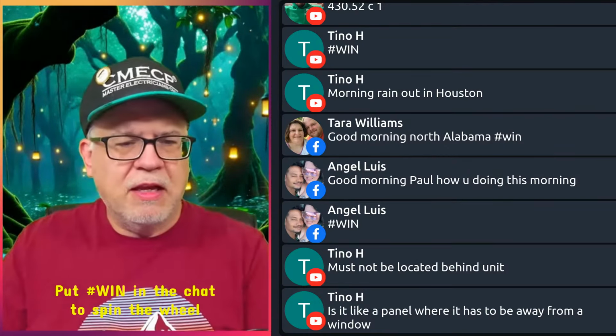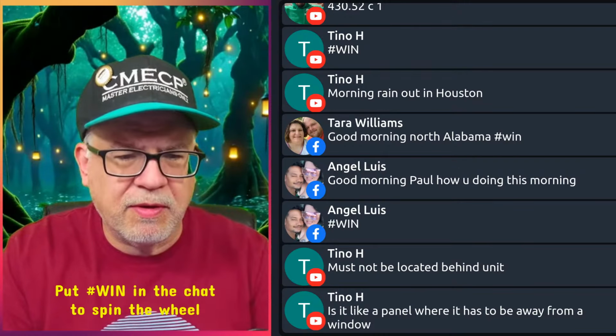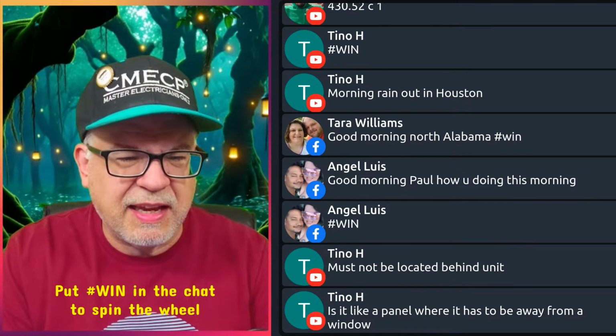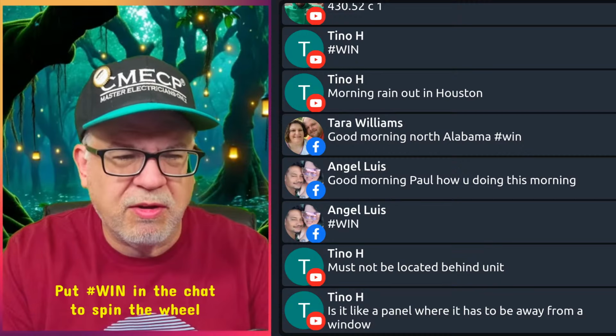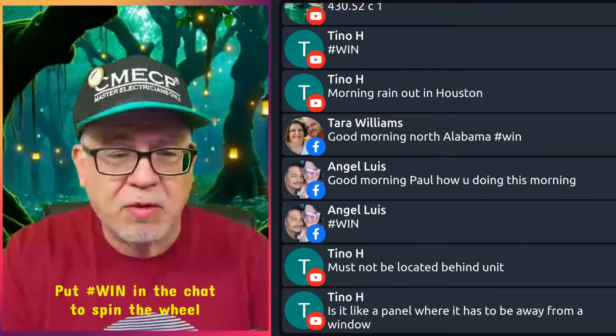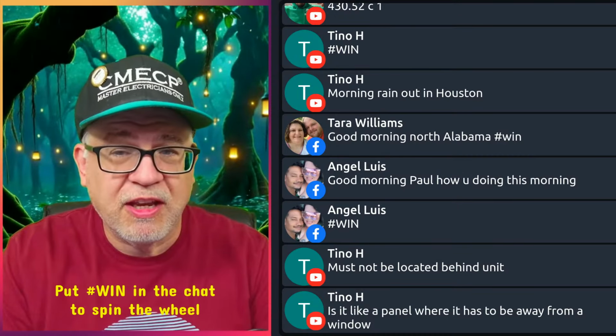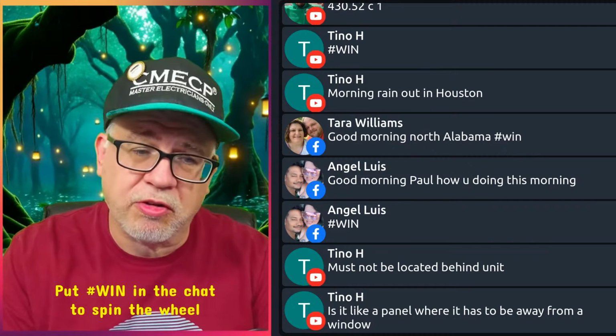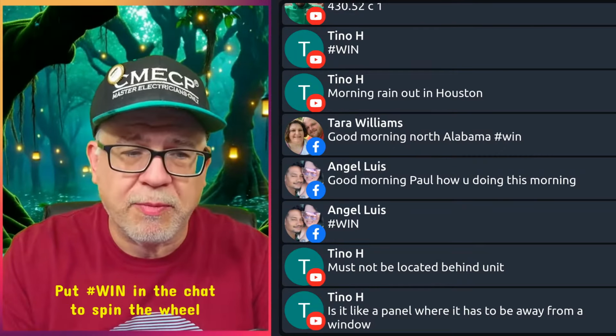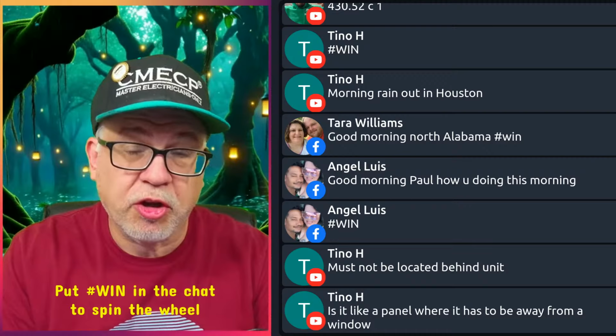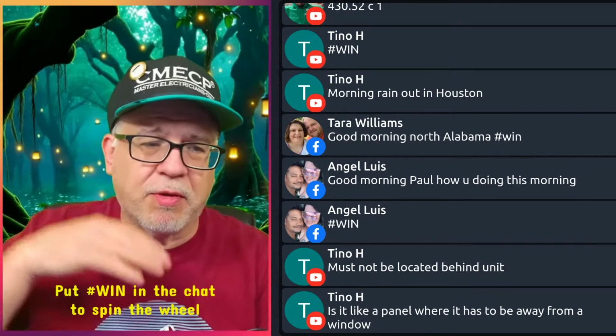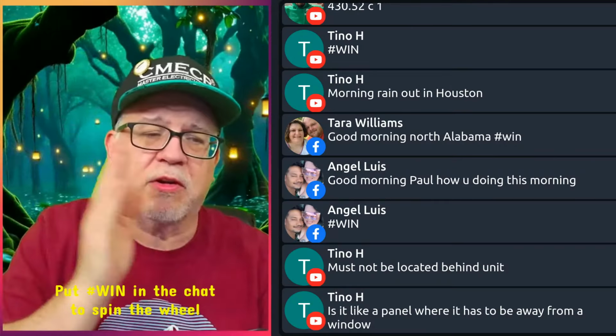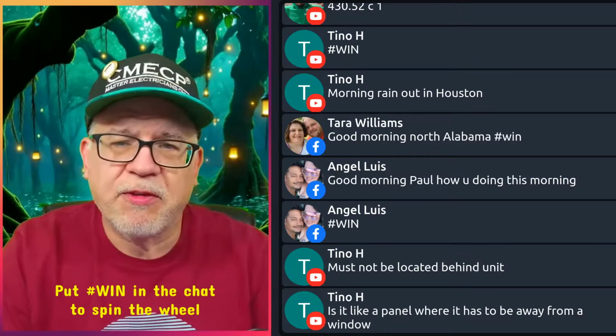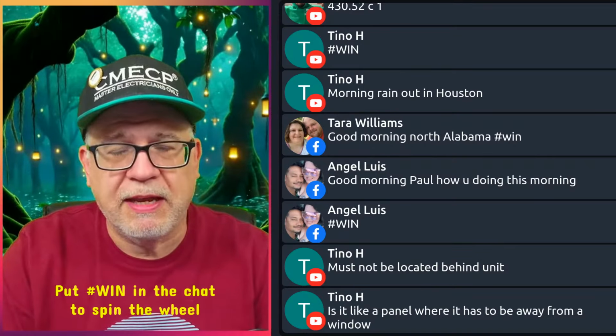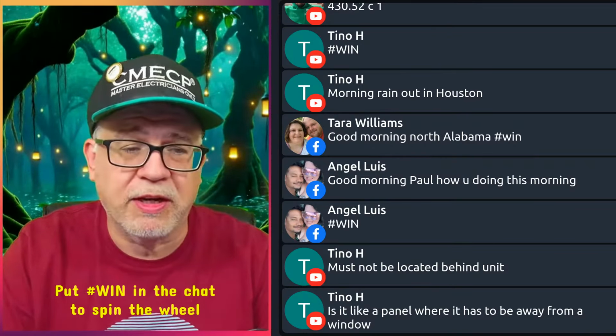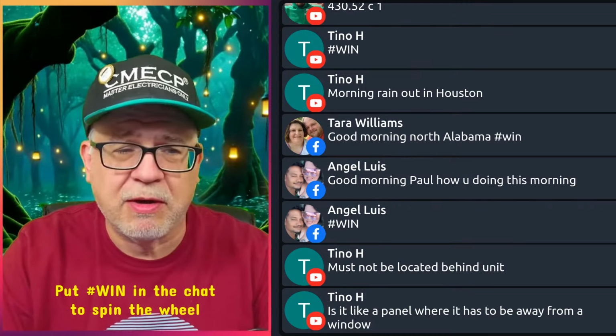Tino says, is it like a panel where it has to be away from a window? There is no rule that says a panel has to be away from a window. It's individual conductors or open conductors that have to be 3 feet away from an openable window. Okay, you can go across the top and be less if the top part doesn't open, right? It's above it. But if you're to the side and front, if it's open conductors, you have to be 3 feet away. If it's in a raceway, it can run right by the window. A panel can be perfectly beside a window.